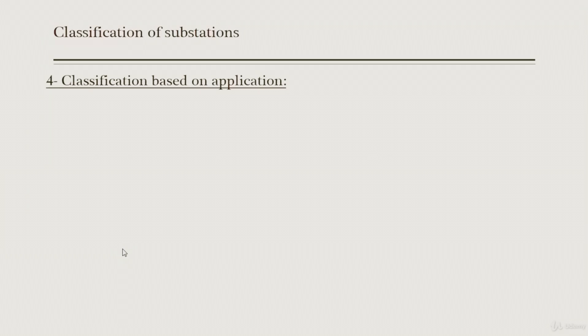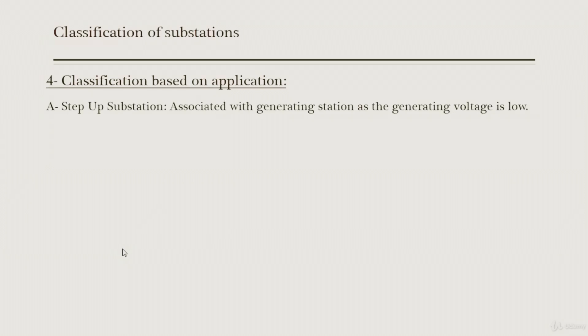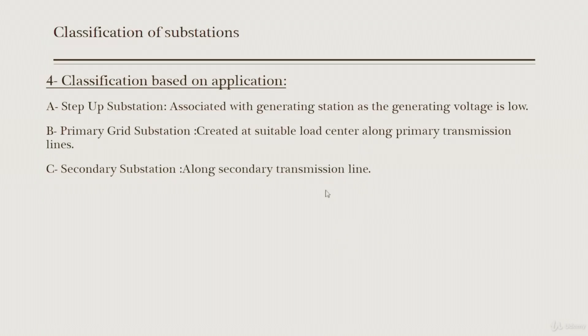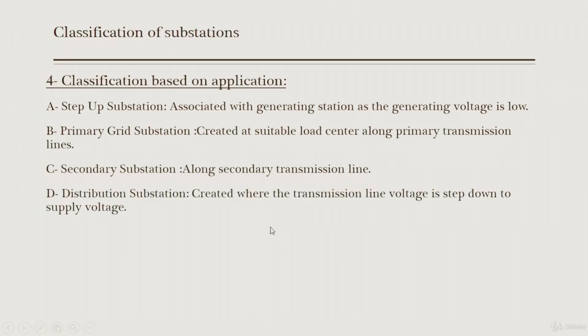The fourth classification is based on application. A step-up substation is used with generating power plants, since the generating voltage is low — for example 3.3 kV or 11 kV — and needs to be stepped up. The primary grid substation is located at a suitable load center along the primary transmission lines. The secondary substation is located along the secondary transmission lines.